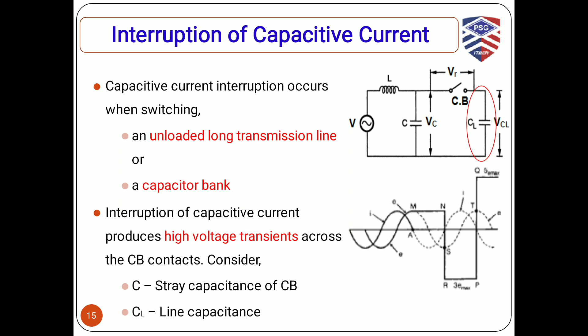For better understanding, there are two instants we are going to consider. At the instant M, the capacitive current is zero. There are two waves you could see in dark lines, I and E. I is the capacitive current in this case, and E is the system voltage. So at the instant M, the system voltage is maximum and the capacitive current is zero. If the interruption occurs at this moment, CL is still charged to the maximum voltage. The resultant voltage that appears across the circuit breaker contacts, VR, is the difference between VC and VCL.